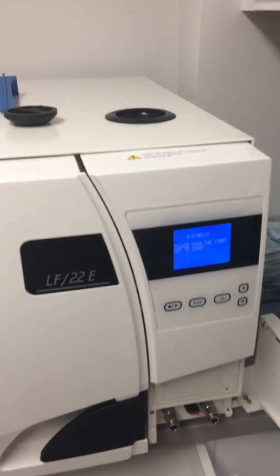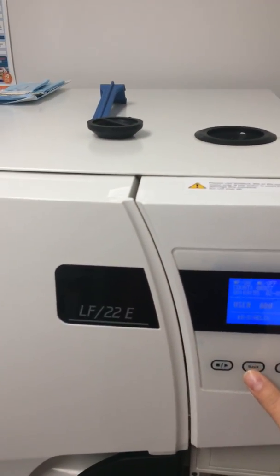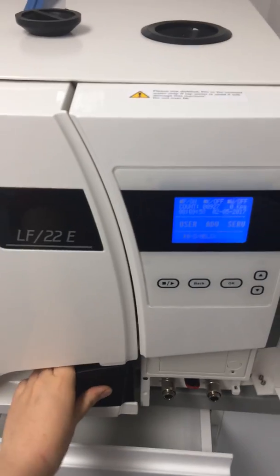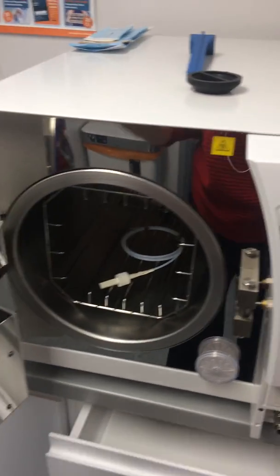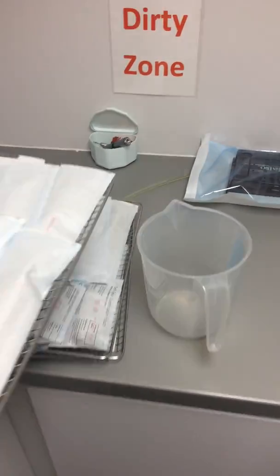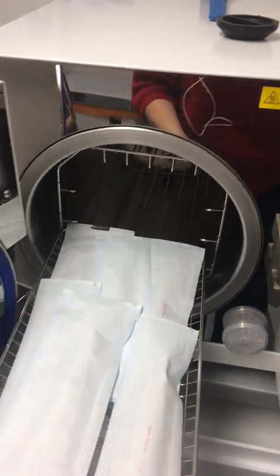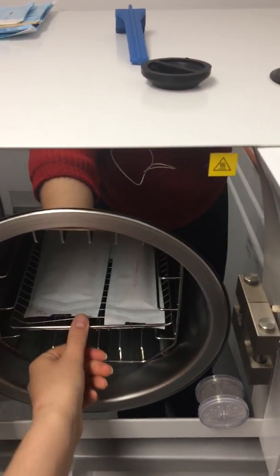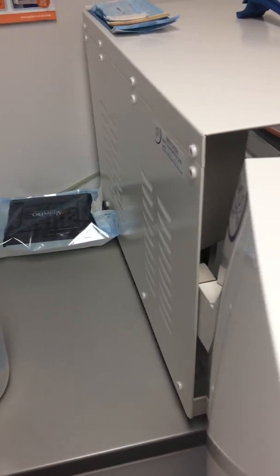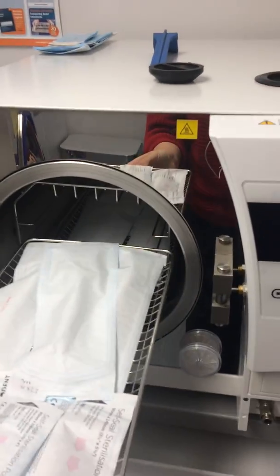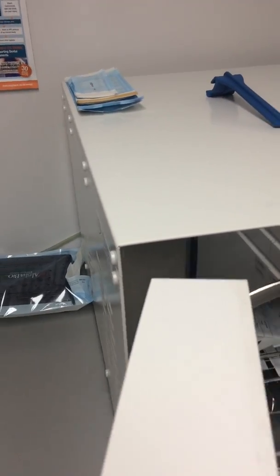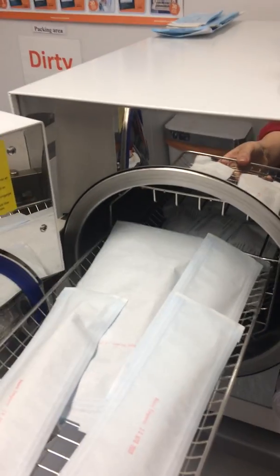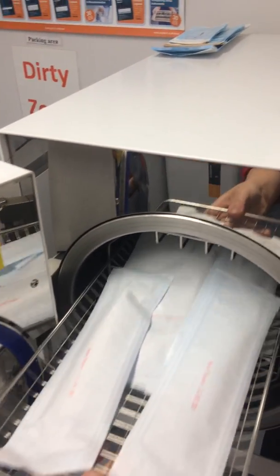So after we have completed the test cycle, we can start and do our daily instruments. We have here already prepared ones, so we place them. As you can see, instruments can't overlap much, so steam can go through all the levels. If there are too many instruments on the first level, the third level won't get enough steam and the sterilization process will be considered failed.